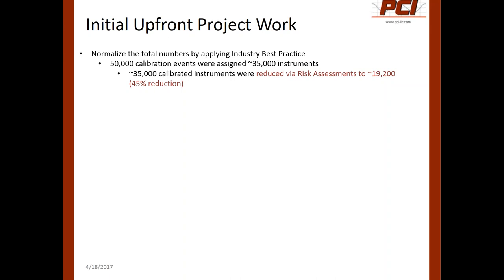And then for all instruments that were non-critical, we decided we were not going to perform a calibration with a pass-fail output. Instead, we decided we would have a preventive maintenance program against those types of instruments. If the site wanted to, they could manage it their own way.